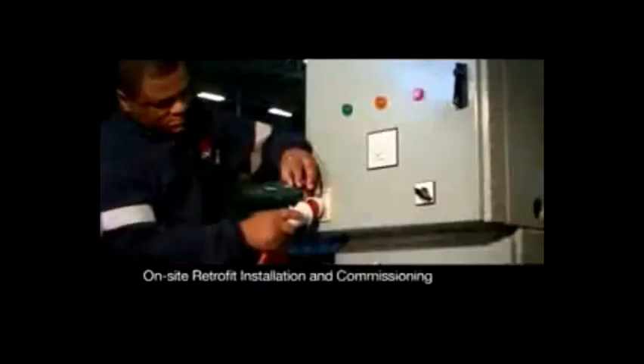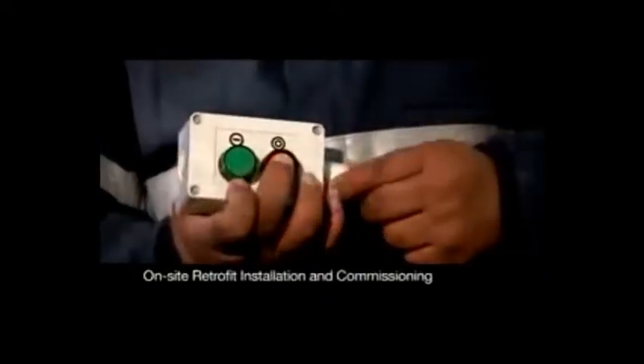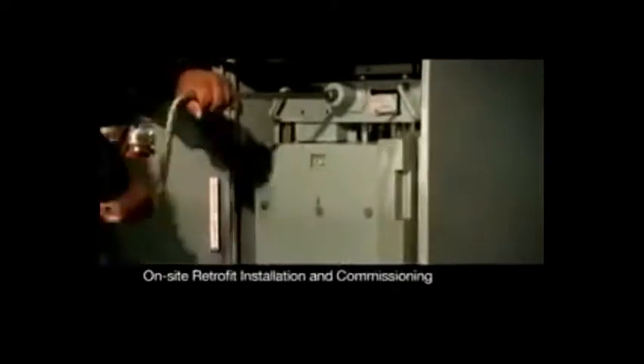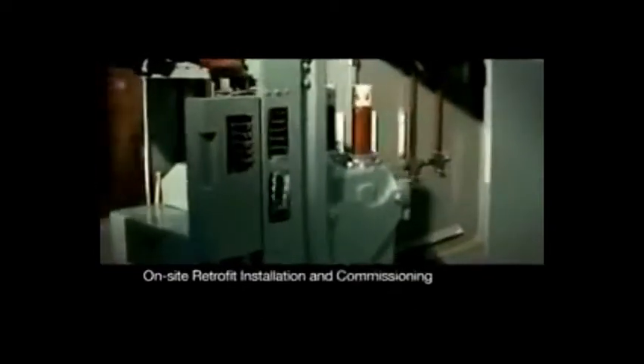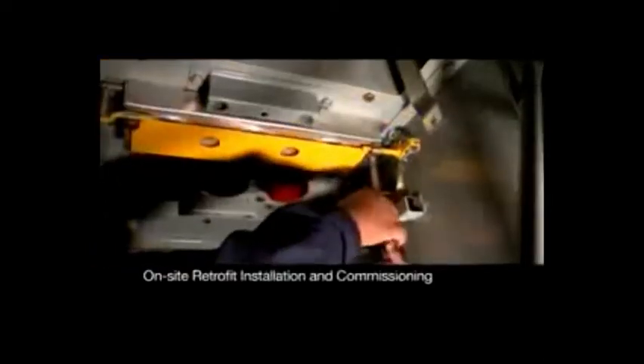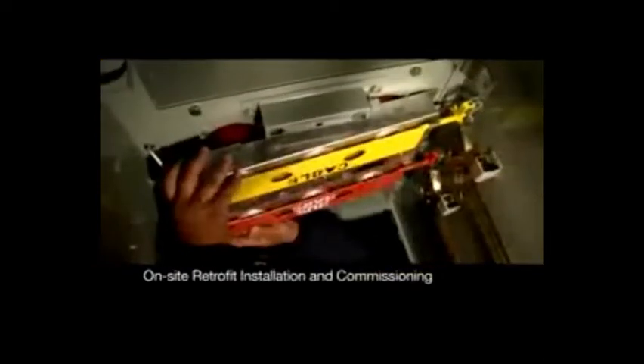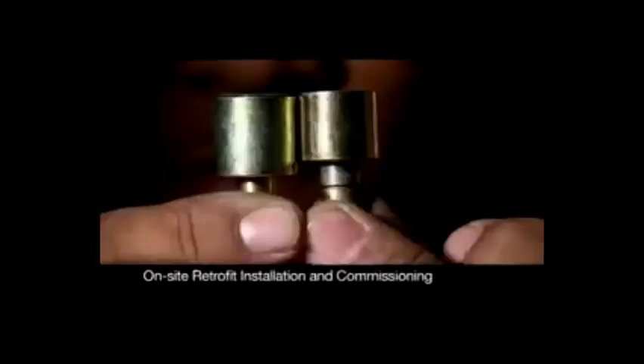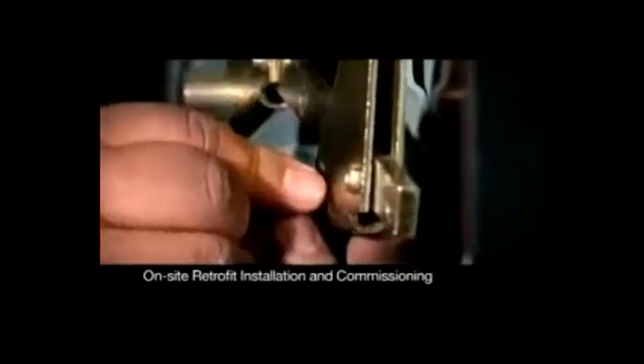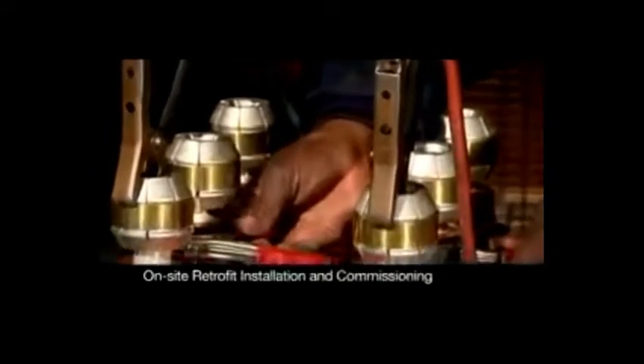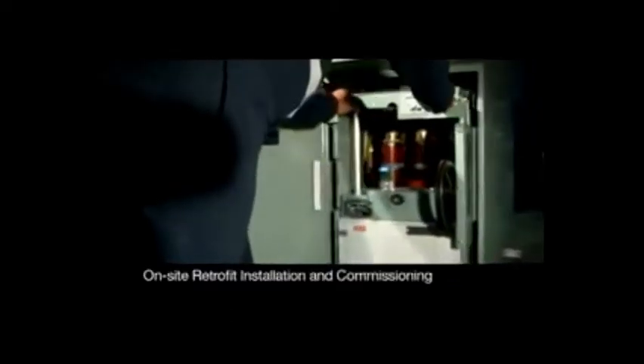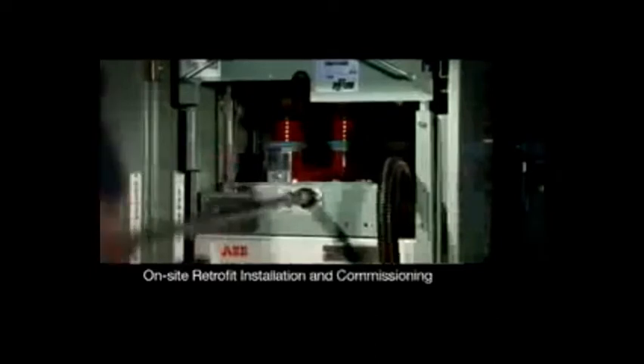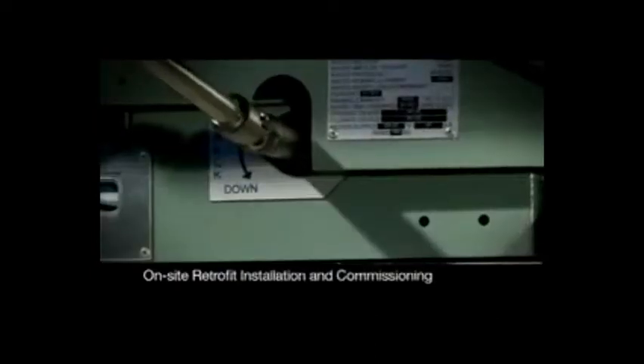Our qualified technicians make the installation safe for site work and remove the circuit breaker from the switchgear cubicle. The existing shutter boxes are removed and a new combined shutter box is installed. Slightly longer, new shutter drive pins are fitted to improve the shutter engagement. A pre-commissioning test is completed before installation. Site commissioning tests are completed before the new VD4 LMT circuit breaker is inserted into service.